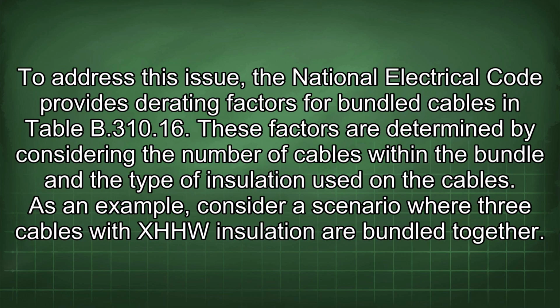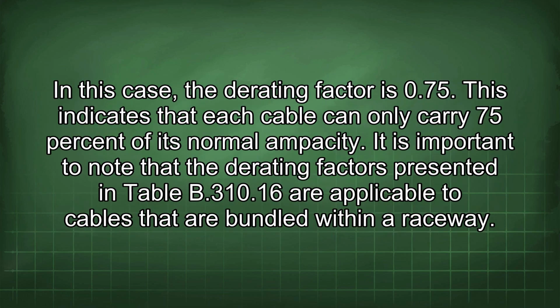To address this issue, the National Electrical Code provides derating factors for bundled cables in Table B 310.16. These factors are determined by considering the number of cables within the bundle and the type of insulation used on the cables. As an example, consider a scenario where 3 cables with XHHW insulation are bundled together. In this case, the derating factor is 0.75. This indicates that each cable can only carry 75% of its normal ampacity.